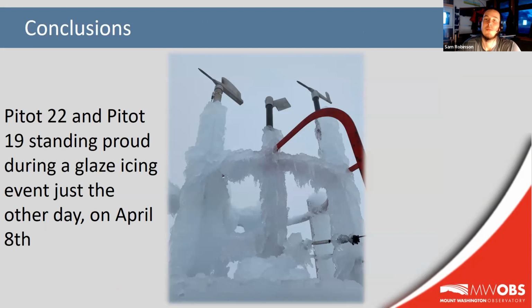So at this point in time, we are pretty satisfied with the performance of the next generation anemometer, pitot 22, and we look forward to finishing up the final stages of this instrument becoming our primary pitot tube anemometer up here on the summit. We're planning on continuing to run it alongside our other anemometers to further compare its performance and also to finalize any last minute changes to the instrument that we might need to make in order for it to be as accurate as possible. We do hope to have it set as our primary instrument this spring after finishing up our internal report on it and then getting approval from the National Weather Service.